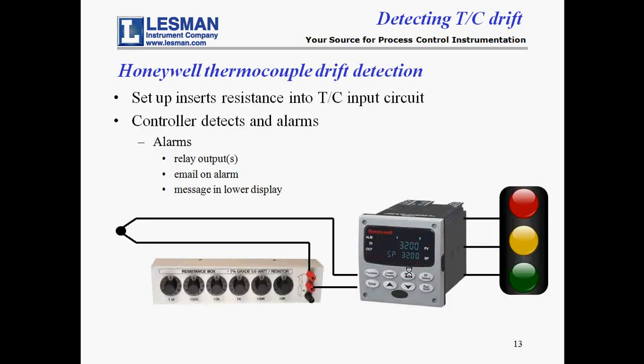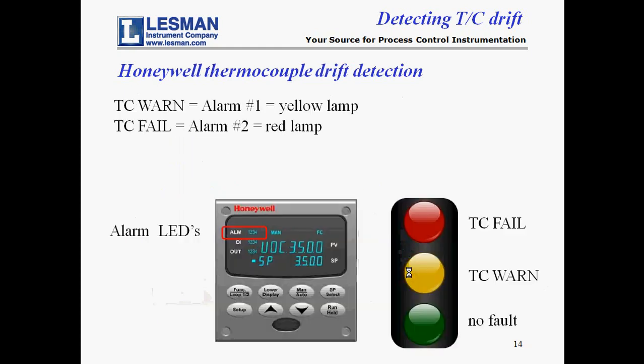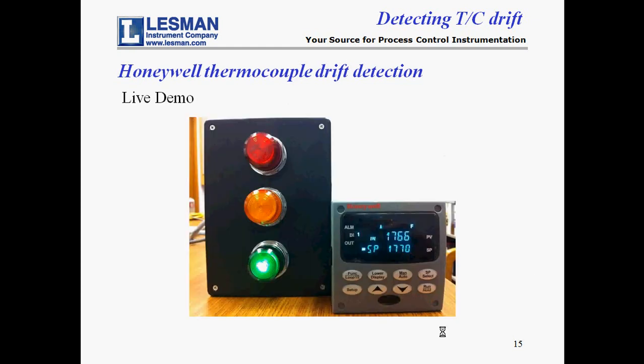This is a diagram of the simulated drift detection with a UDC controller. A decade resistance box is used to simulate a polluted high-resistance thermocouple junction in order to demonstrate the drift alarm. The alarm outputs are wired to an alarm enunciator that looks like a traffic light. On the UDC faceplate, the temperature is shown in the upper display, the setpoint is shown on the lower display, and the LED indicators in the upper left indicate the alarm status. Alarm number one is TC WARN and alarm number two is TC FAIL. The green lamp, when it turns on, indicates no fault.